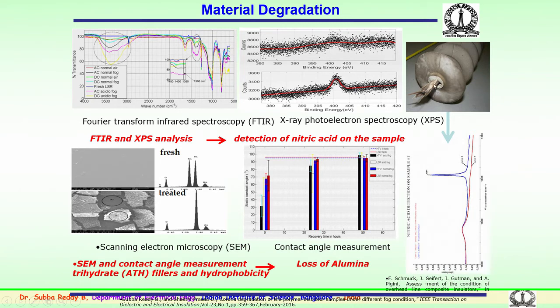Similar to that, there have been reports that brittle fracture could occur. So, this brittle fracture could be because of the formation of nitric acid, which could enter the surface inside the fiberglass rod, and the failure of the fiberglass rod could happen. So, this gives the X-ray XPS analysis, where it shows the number of counts versus the binding energy. So, we see that there is a difference for the fog and for the normal type of application, that is, without fog.